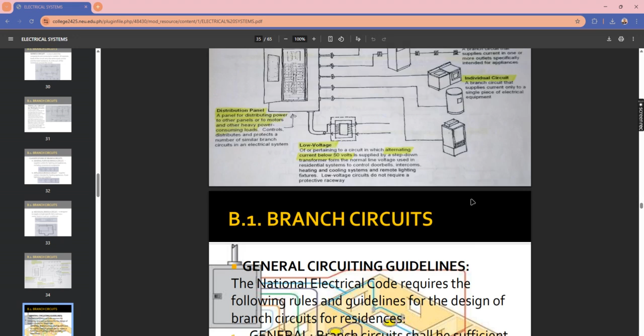Branch circuits: these are the requirements for 30 watts per square meter, up to 80 square meters for a 20 ampere circuit. You can see here that the total consumption or total watts for a 60 square meter, 15 ampere circuit is 1,800 watts.